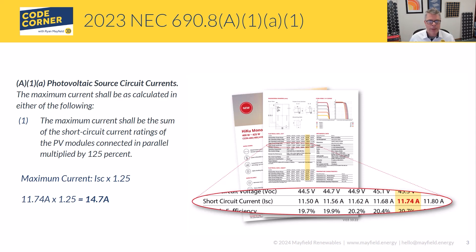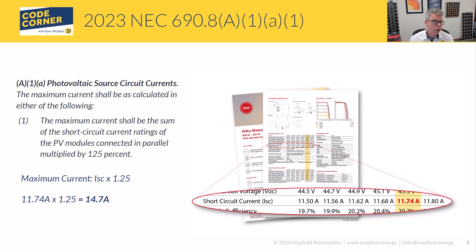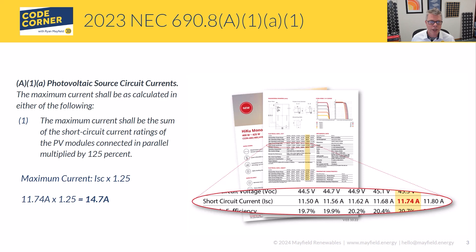I encourage people to go through this step by step — don't try to jump ahead when applying correction factors, because the risk is applying too many correction factors to your calculations and ultimately oversizing your wire. So this first step is multiplied by 125%. We'll talk in a future video about 690.8B and how to apply these values, but right now just know that maximum current is what we're trying to get after, and this is how you get it for your PV source circuits.